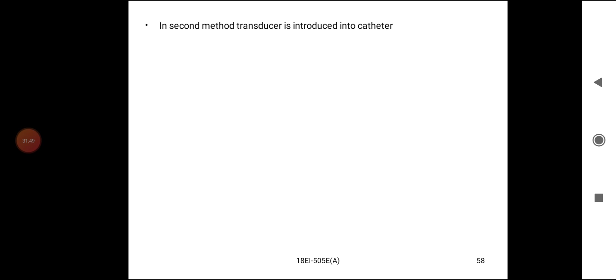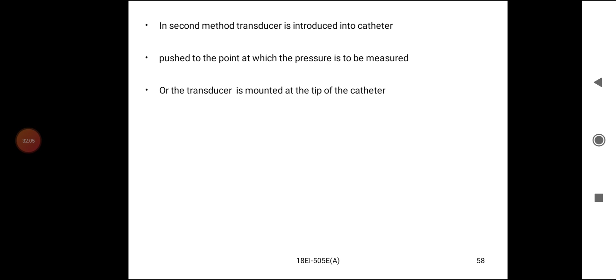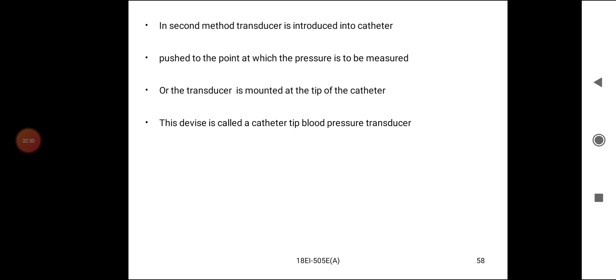In the second method, a transducer is introduced into the catheter and pushed to the point at which the pressure is to be measured, or the transducer is mounted at the tip of the catheter. The device is called a catheter tip blood pressure transducer.